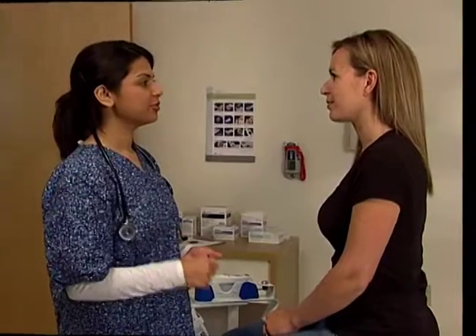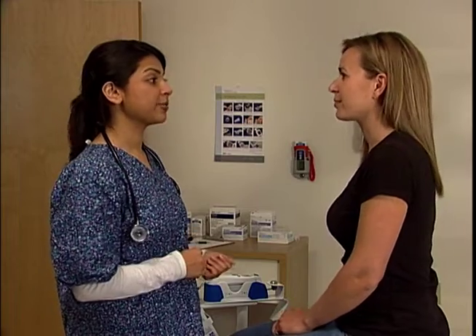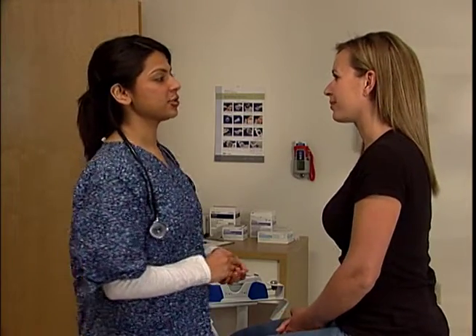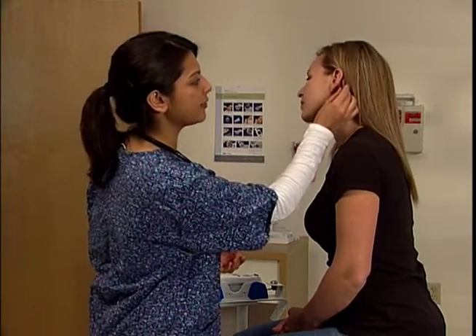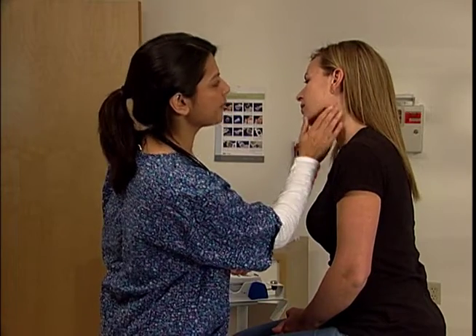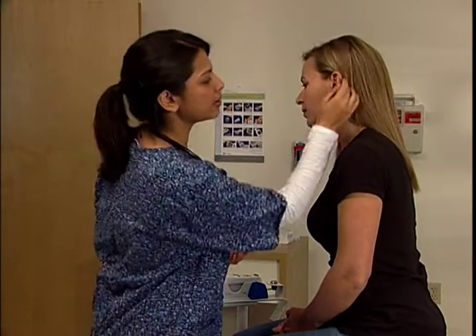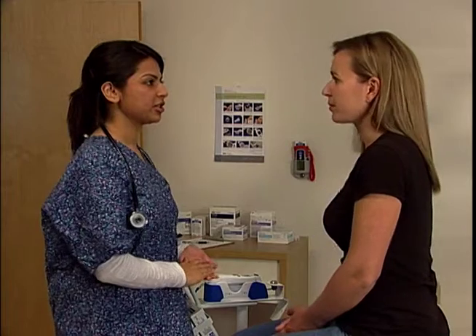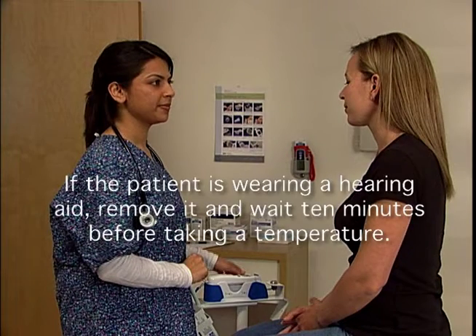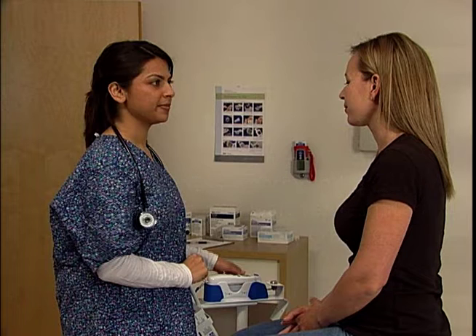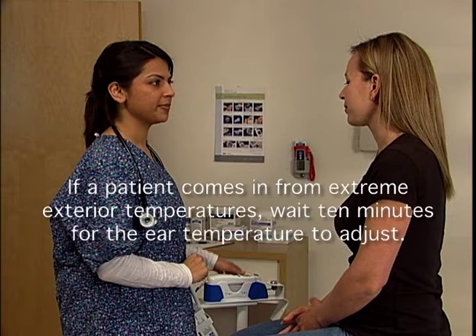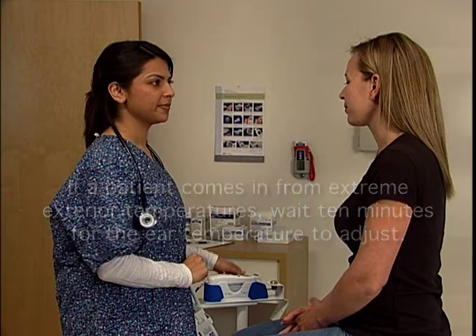To perform a reading, first inspect the patient's ear anatomy for proper placement of the probe tip. Make sure the patient's ear is free of blood or any other fluid. The ear should have no obstruction and should be free of impacted earwax. If the patient is wearing a hearing aid, remove it and wait 10 minutes before taking a temperature. Patients coming in from extreme exterior temperatures may exhibit an inaccurate ear temperature. You should wait 10 minutes for the ear temperature to adjust.